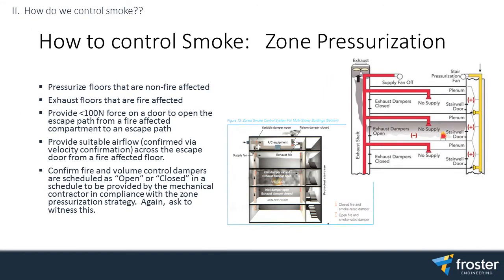This is an interesting one. So 1668 and 1998 gave you a number of options based on classification of building, how many floors. This new standard really simplified it. It's allocated all of those options into zone pressurization. So it's putting more responsibility on the fire engineer and the mechanical consultant to work out the strategy. But this typically is the preferred strategy in a building over 25 meters.